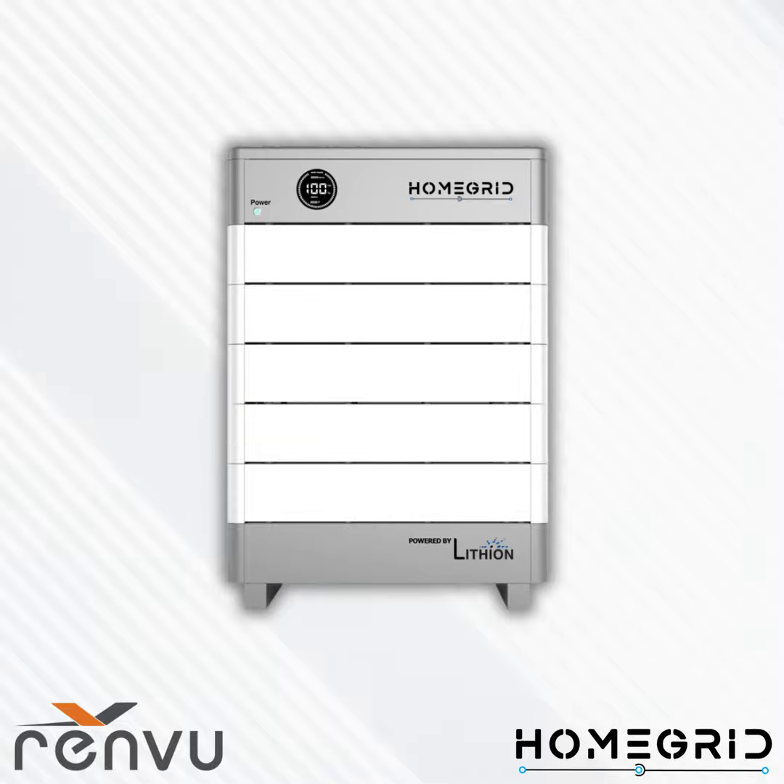There is a HomeGrid and SolarC settings guide available online. Most settings happen automatically when you connect SolarC and HomeGrid batteries. The one thing you will need to manually set on the battery tab in the battery setup screen is the correct battery capacity — the total kilowatt-hour capacity based on how many modules and stacks you have. For a four-module stack, that's 19.2 kilowatt-hours. Set max charge and discharge to 275 on those two settings.